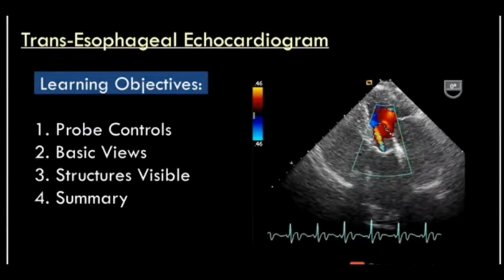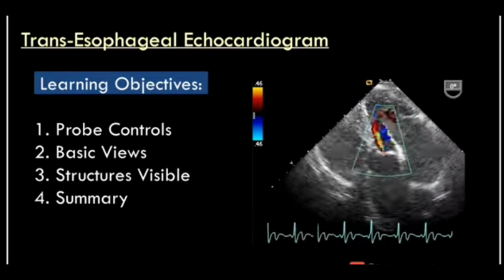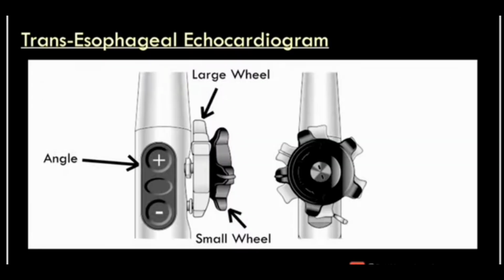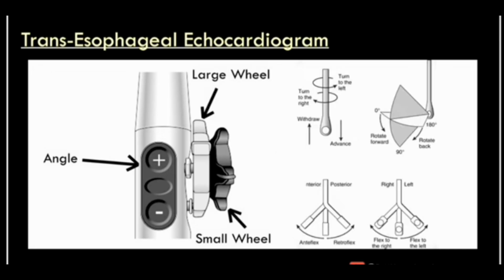Basic views of transesophageal echocardiogram and the structures visible in each view. Transesophageal echo probe typically has a large control wheel, a small control wheel, and knobs to adjust the angle of the ultrasound beam. Physical probe manipulation can be performed by turning the large control wheel on the handle to anteflex or retroflex the probe. Furthermore, the tip of the probe can be flexed left or right by rotating the smaller control wheel. The shaft of the probe can be advanced or withdrawn.